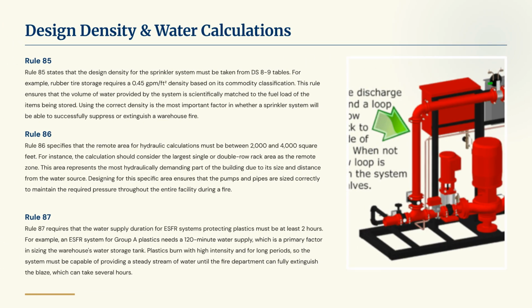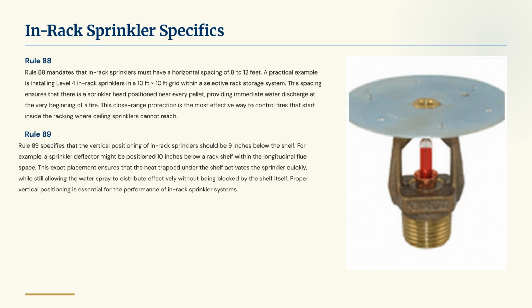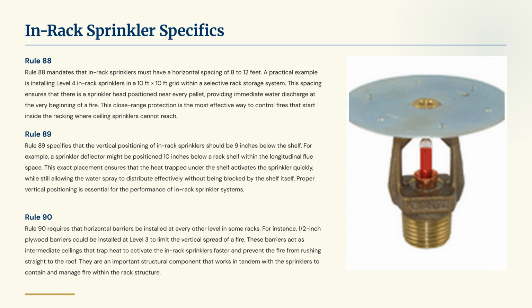Rule 85 states design density must be taken from DS8 to 9 tables, matched to the commodity. Rule 86 specifies the remote area for hydraulic calculations must be 2,000 to 4,000 square feet. Rule 87 requires a minimum 2-hour water supply duration for ESFR systems protecting plastics. Rule 88 mandates 8 to 12 feet horizontal spacing for in-rack sprinklers.